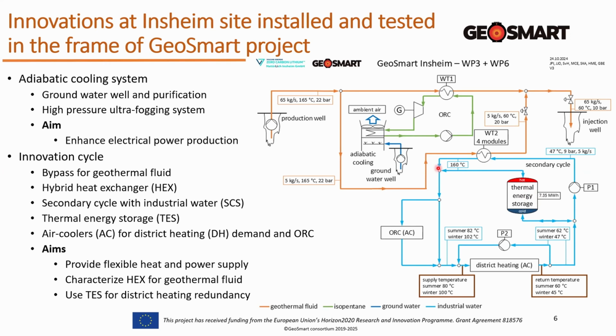The hybrid heat exchanger, this WT2 here, consists of 4 modules, and it's a new technology that we want to test within the project. It's a plate heat exchanger which forms tubes on one side. This is how we expect it could be cleaned, because other tests with normal plate heat exchangers showed that with the geothermal fluid in the upper Rhine graben, this is not feasible. So the aims are for this innovation cycle to provide flexible heat and power, to characterize the hybrid heat exchanger, and to use the thermal energy storage for redundancy at the district heating.